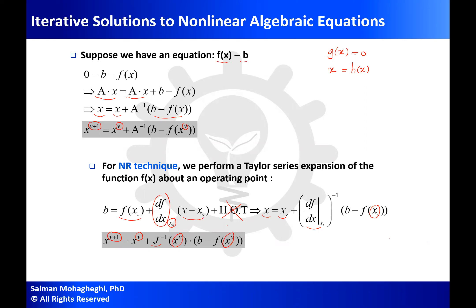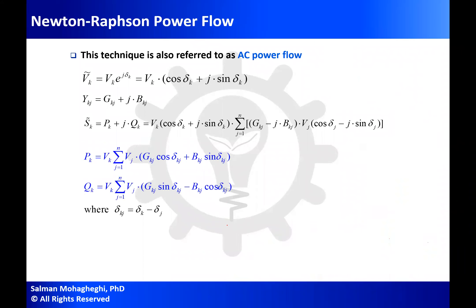Here, like before, you start with initial conditions to find x(1), plug in x(1) to find x(2), and continue this process. How do we apply this to AC power flow? Recall that we had an equation of the form S̃_k = Ṽ_k times the conjugate of the summation over j from 1 to n of Y_kj Ṽ_j. This is what I had for the Gauss and Gauss-Seidel techniques.